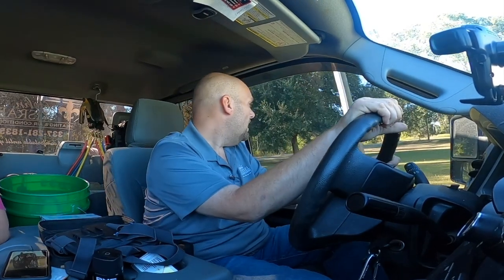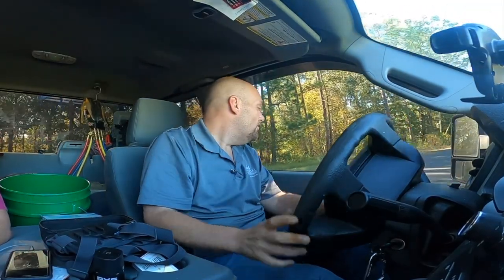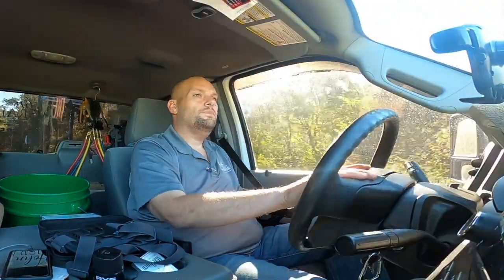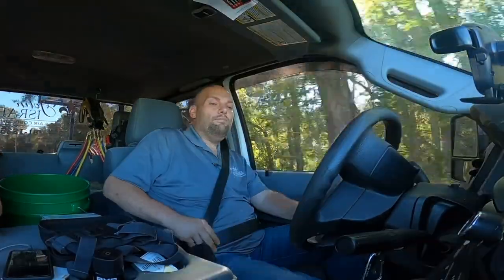I also remember now that I'm here that I ran a leak detector on his evaporator coil and he needs an evaporator coil. So that'll be the next thing. But I do hope you guys enjoyed the video. It was better than nothing. Just changed out a quick sequencer and got his heat working. The sequencer was stuck, so the minute you'd apply power to the furnace, the 5 kW would come on with the blower. Anyway, it's done and he's got air and heat that's not running together, and he's happy.